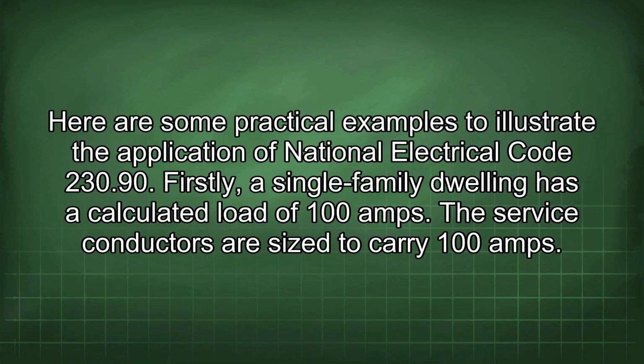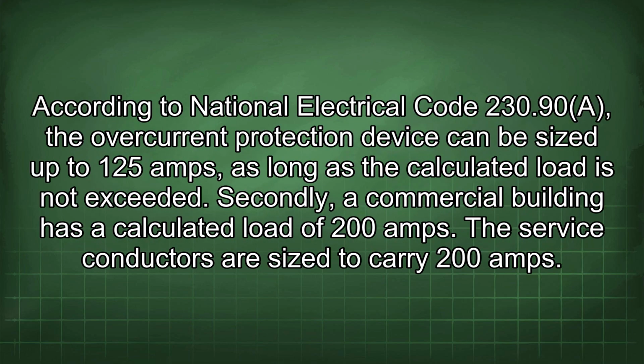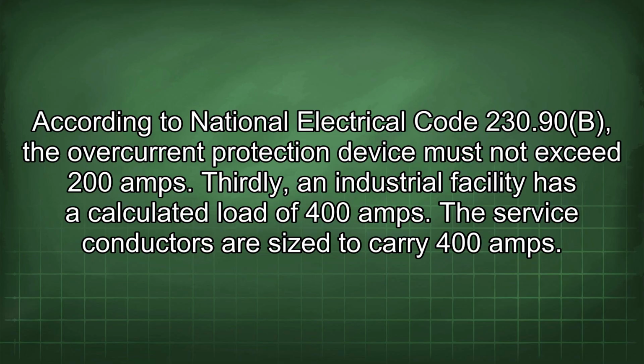Here are some practical examples to illustrate the application of National Electrical Code 230.90. Firstly, a single-family dwelling has a calculated load of 100 amps. The service conductors are sized to carry 100 amps. According to National Electrical Code 230.90a, the overcurrent protection device can be sized up to 125 amps as long as the calculated load is not exceeded. Secondly, a commercial building has a calculated load of 200 amps. The service conductors are sized to carry 200 amps. According to National Electrical Code 230.90b, the overcurrent protection device must not exceed 200 amps.